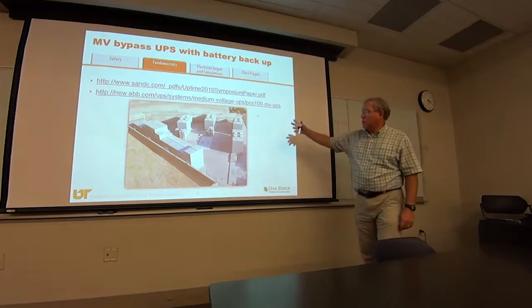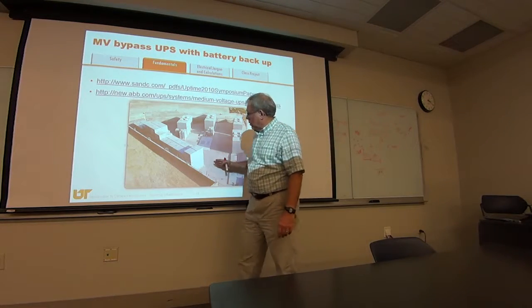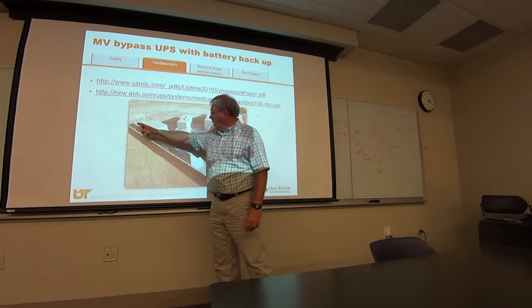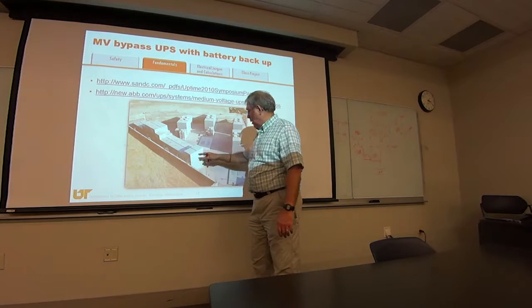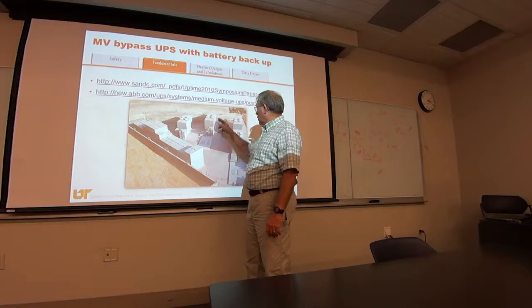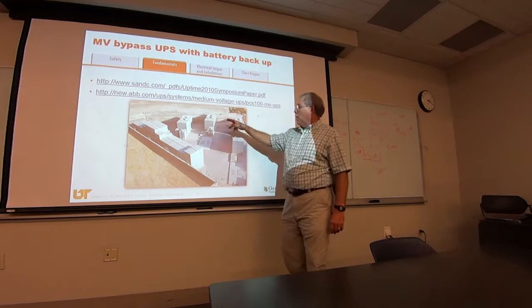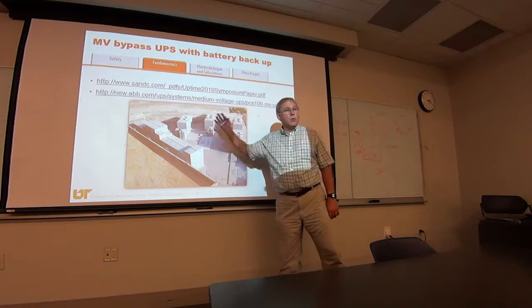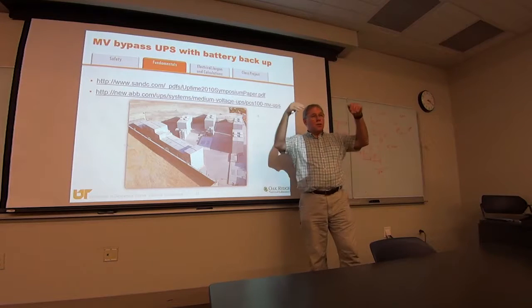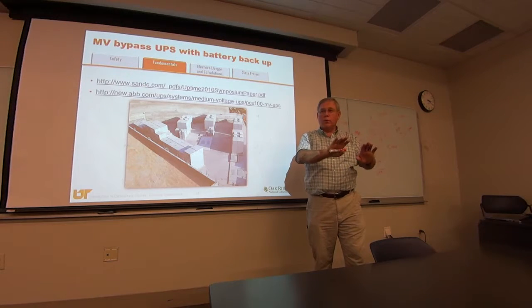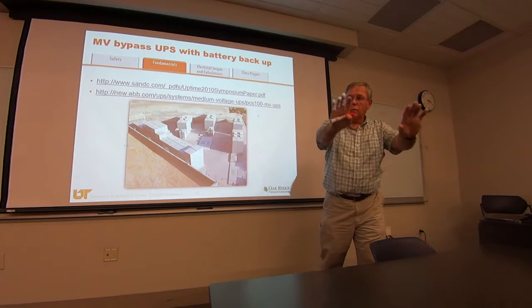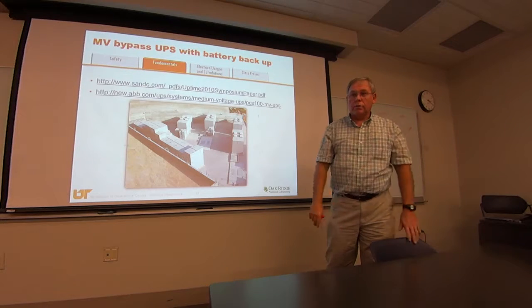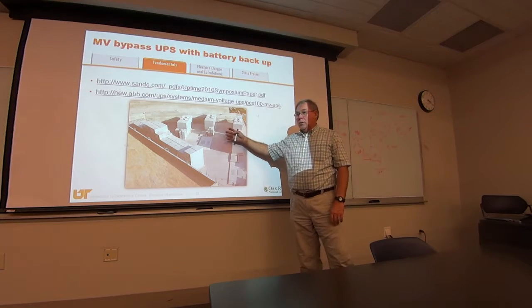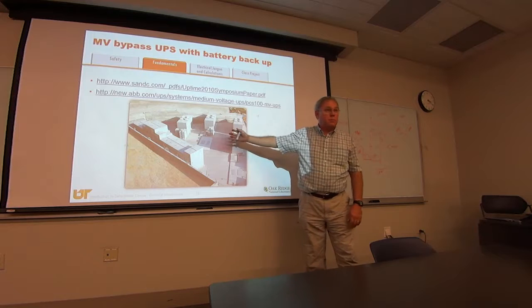This is a medium voltage UPS, S&C. This is the medium voltage switchgear. Your incoming lines down here, your outgoing lines here, and then it feeds to these 4 modules. These are 2 megawatt each. So this is an 8 megawatt UPS. And it's basically taking the utility service, running it through the UPS, and then sending it into the building for computers, chillers, or whatever else. In other words, this one will last about a minute, okay?